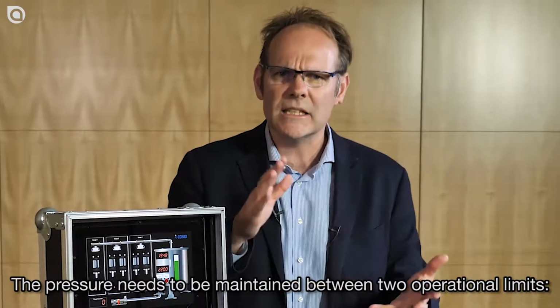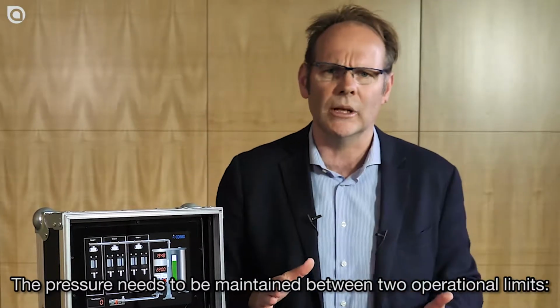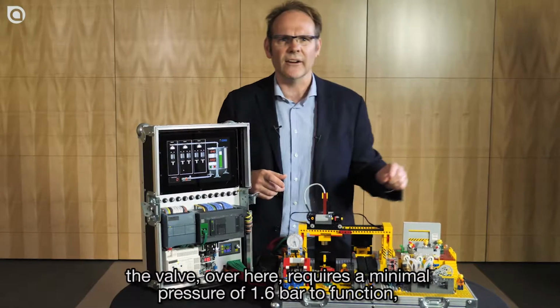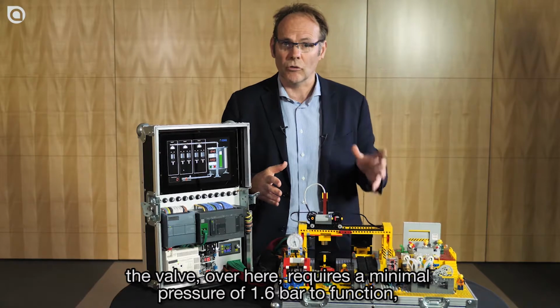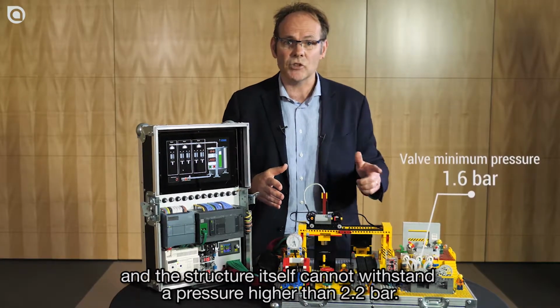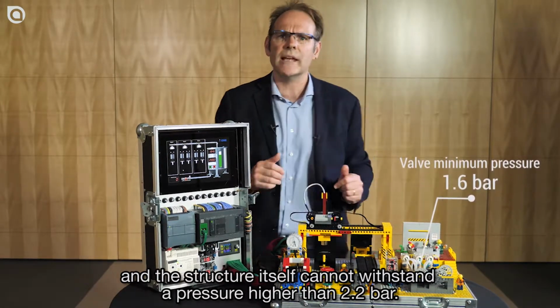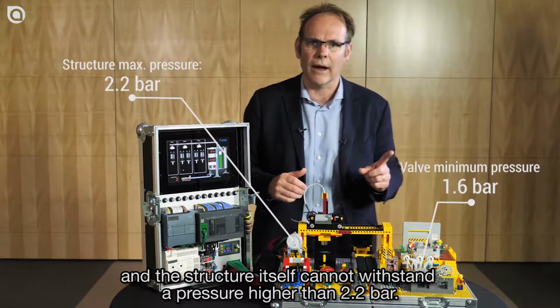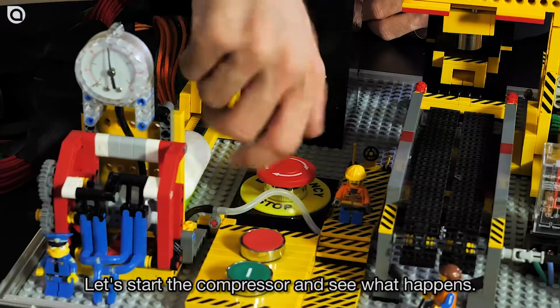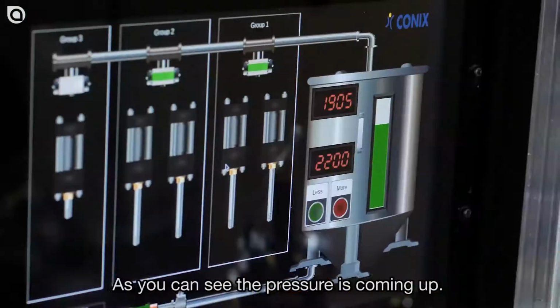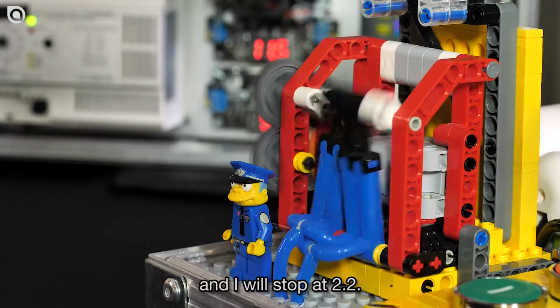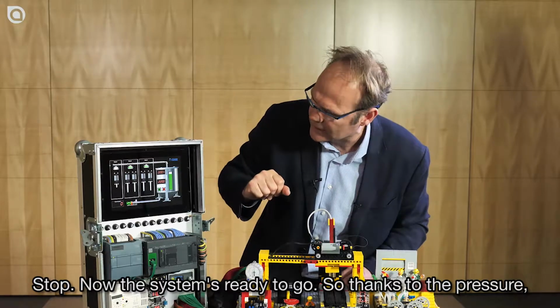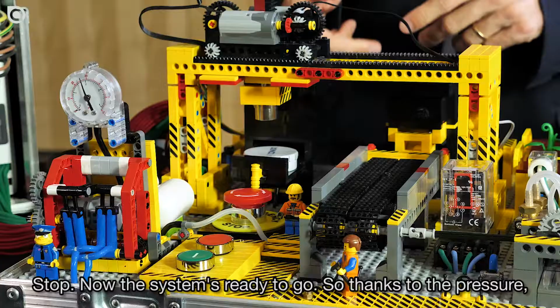The pressure needs to be maintained between two operational limits. The valve over here requires a minimal pressure of 1.6 bar to function, and the structure itself cannot withstand a pressure higher than 2.2 bar. So let's start the compressor and see what happens. As you can see, the pressure is coming up and it will stop at 2.2 and stop. Okay, now the system's ready to go.